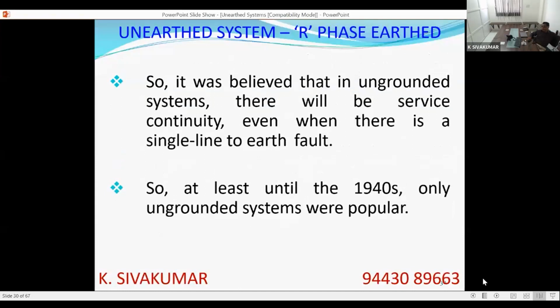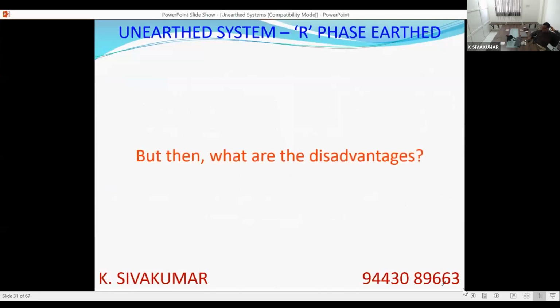So at least until the 1940s, perhaps until the Second World War, only ungrounded systems were popular. The other day I was seeing a reference to the Cahier Technique of Schneider Electric. In it, there is a book on the evolution of earthing, and that also very clearly says that up to the 1940s, unearthed systems were very popular. But if it is so advantageous, with no shock risk, earth fault currents not very high, and service continuity, in spite of all these things we do not practice unearthed systems at all. We are much more familiar with earthed systems. So there must be some disadvantage in the unearthed system. Let us discuss the disadvantages of the unearthed system.